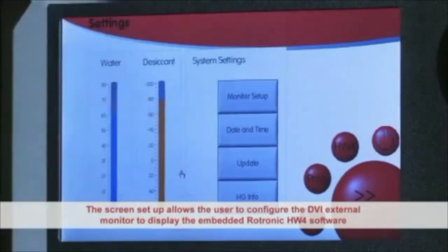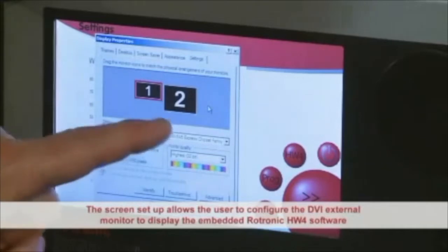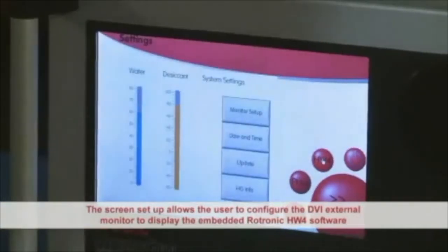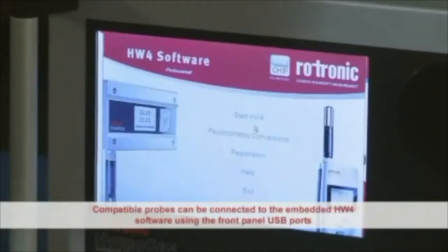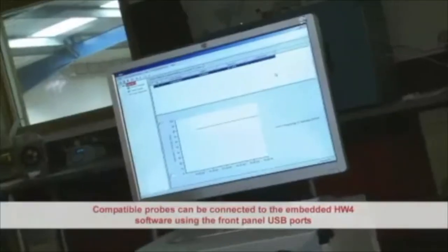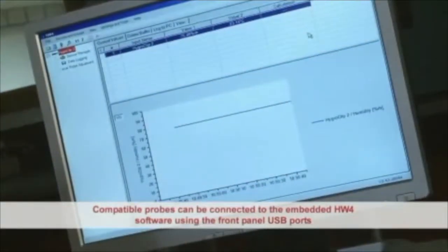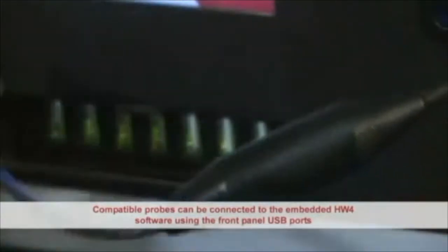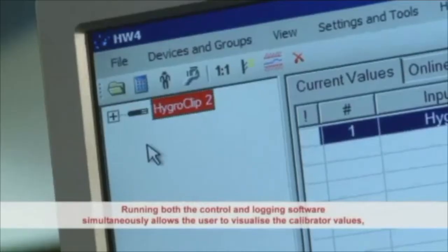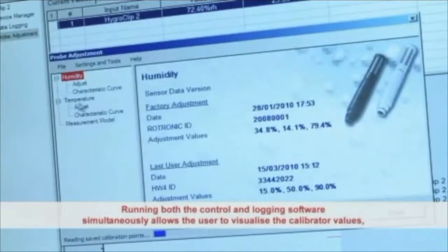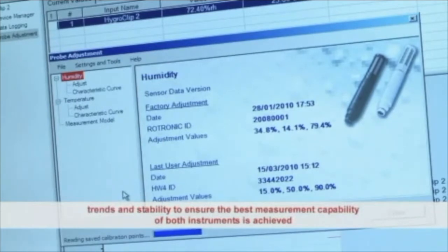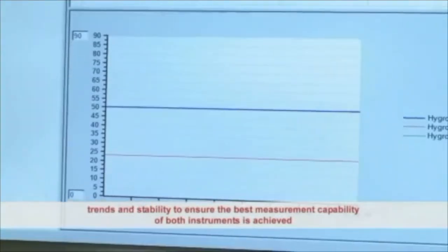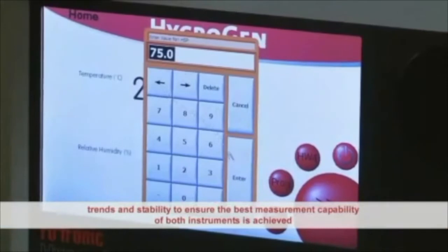The screen setup allows the user to configure the DVI external monitor to display the embedded Rotronic HW4 software. Compatible probes can be connected to the embedded HW4 software using the front panel USB ports. Running both the control and HW4 logging software simultaneously allows the user to visualize the calibrator values, trends and stability to ensure that best measurement capability of both instruments is achieved.